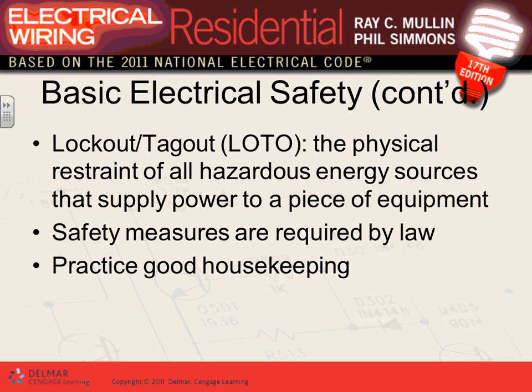You're in an operating room in a hospital, shutting down the switchgear to work on it. Can you shut down the switchgear in a hospital and say, well, today send your patients home? So these are the two conditions under which you can work on energized objects: if you can't troubleshoot them de-energized, and if shutting down the system will create more hazard, like in hospitals. And it is the law. OSHA enforces 70E, so what you're looking at is the law. In Minnesota, we adopt OSHA. So if you see somebody working on an energized object, they're violating the law. Be very aware of that.